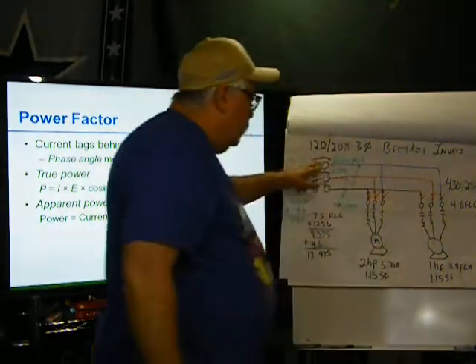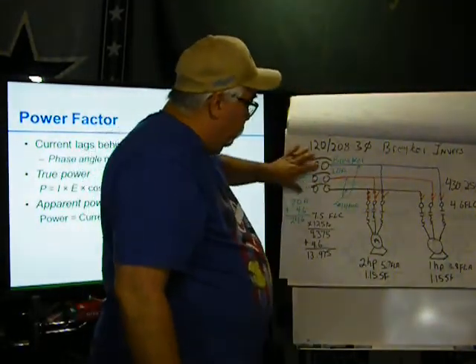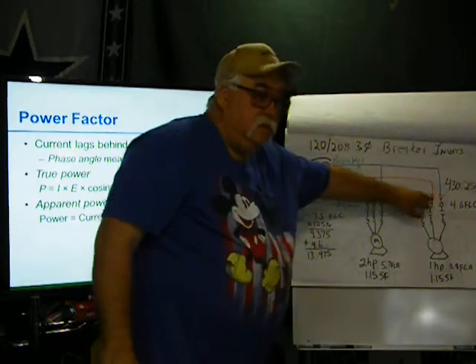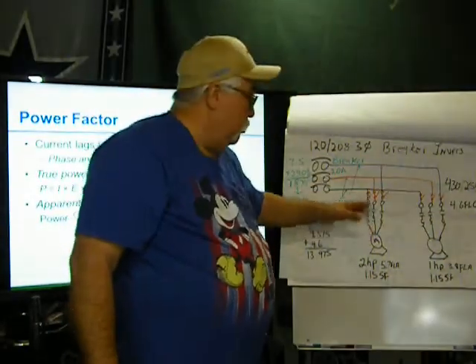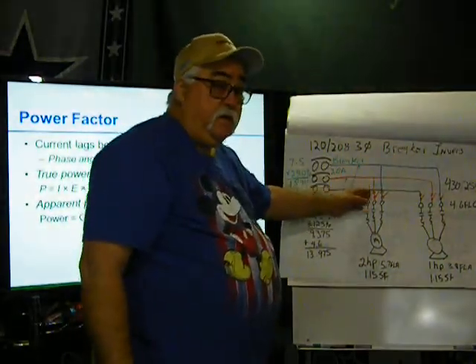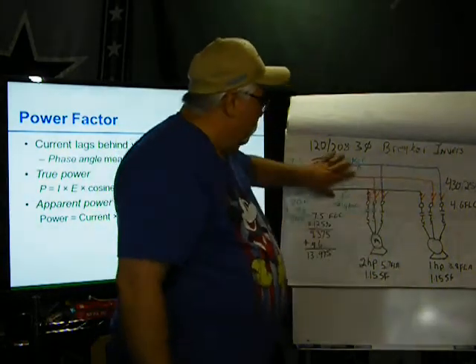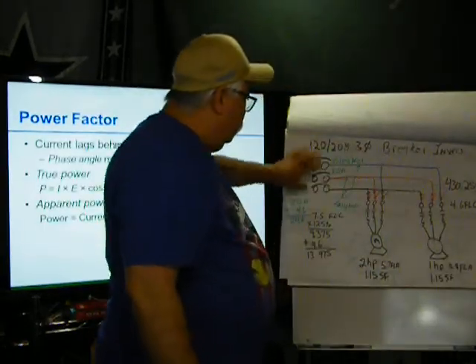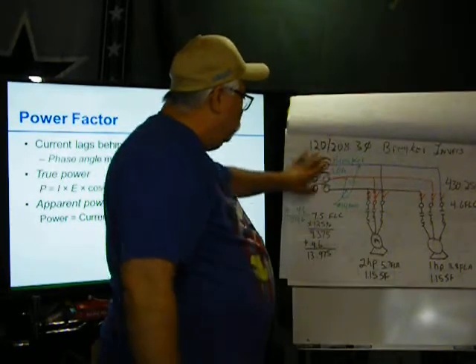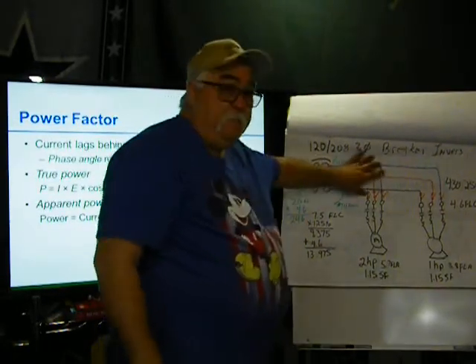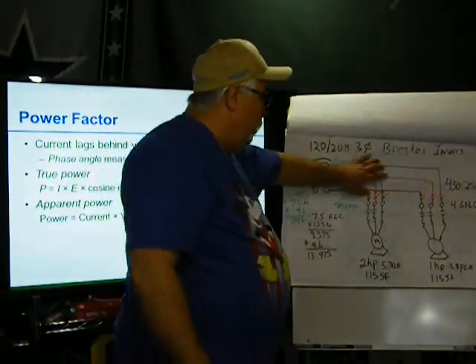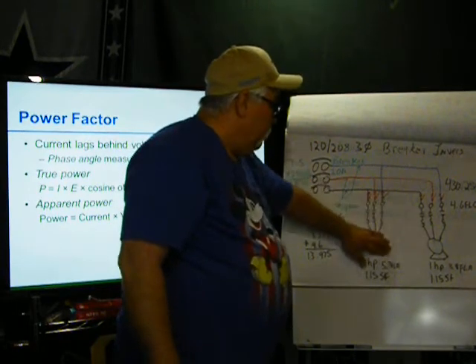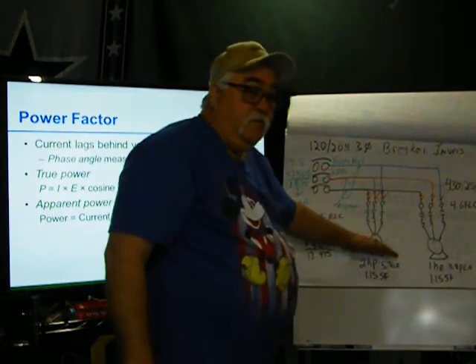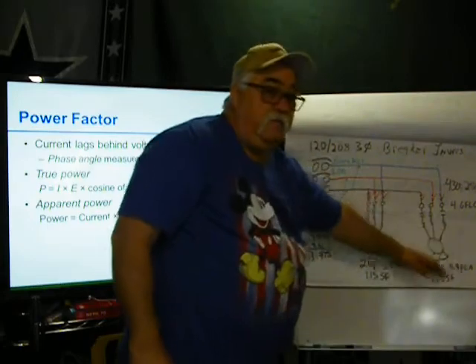Okay, so code says we have a feeder, but we have to have means to protect each motor. So we have to have short circuit protection and ground fault protection at each individual motor. This is a feeder. The only thing we're concerned with when we're doing the feeders, and all these motors come in, is to find the main breaker and the wires. The main breaker and the wire. Okay, once we get down to the motor, from here down, it's an individual motor.